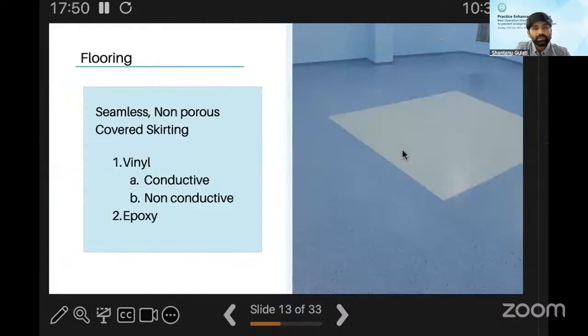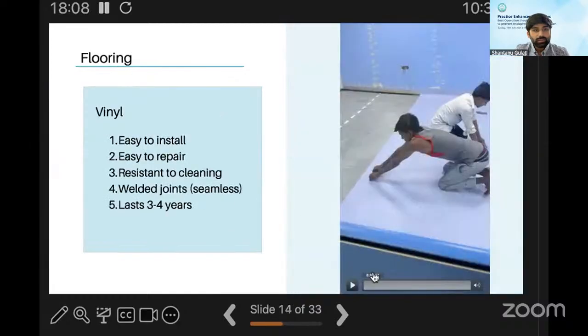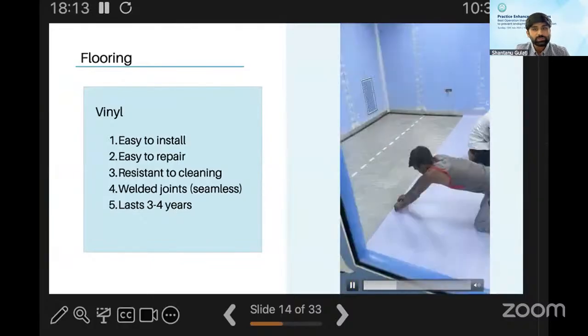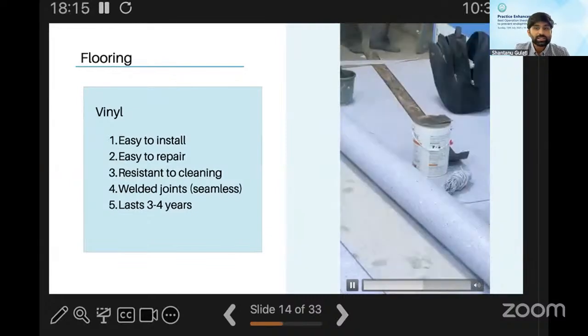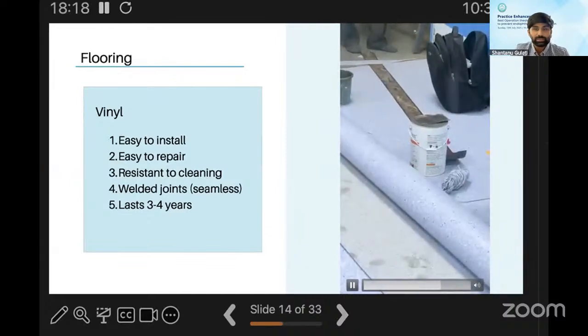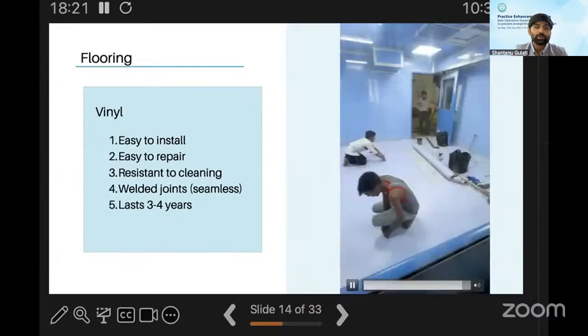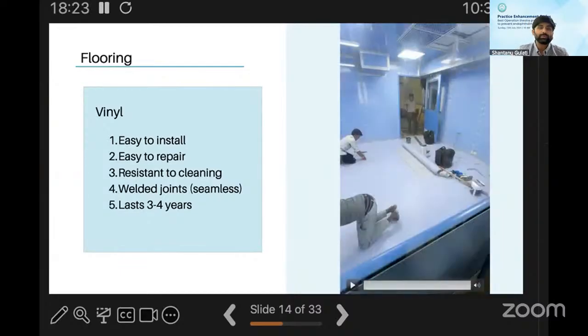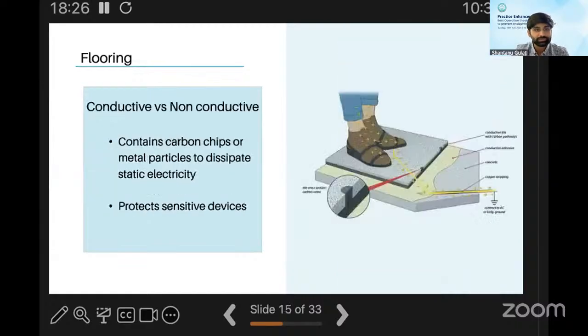So coming to the next thing, that is the flooring. OT flooring has to follow the same surface standards as your walls. The options that are most commonly available are epoxy and vinyl, of which epoxy gives a more seamless finish, but it takes much longer to install and it is more cumbersome to repair. The vinyl option comes in prefabricated rolls that are placed onto a prepped surface with industrial adhesive, and whatever joints are created are then welded together, making it seamless. Even the patchwork here is easier because the patch requiring the patchwork can be just cut out and replaced.